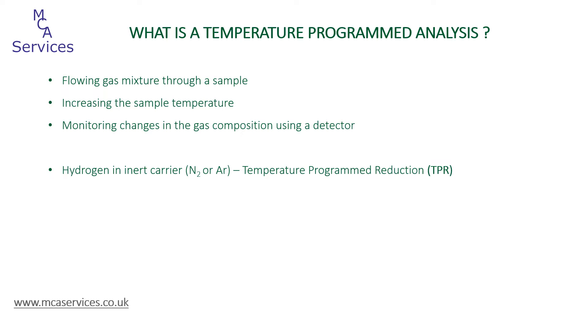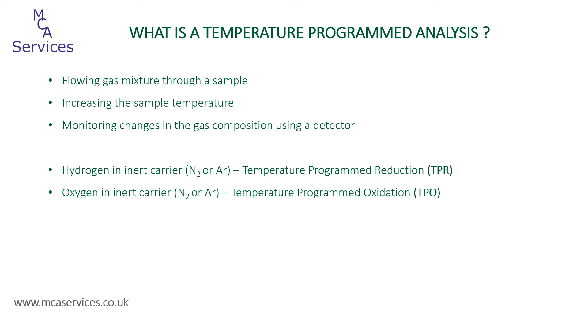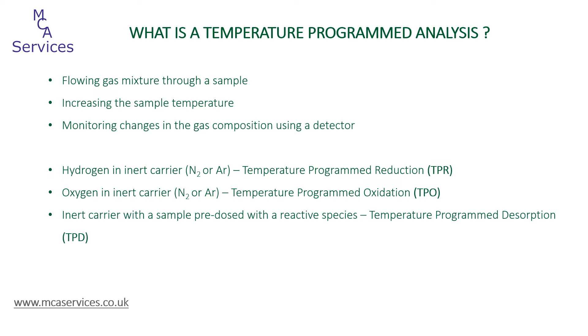Depending on our sample material and the components of the gas mixture, we can perform different temperature programmed analyses. If our sample can be reduced and we have a reducing agent in our gas mixture, for example hydrogen, we can undertake temperature programmed reduction. The opposite — we can oxidise a sample if we have oxygen in the carrier gas. A slightly more complicated analysis is temperature programmed desorption. For this, we pre-adsorb a species of our choosing onto a sample, and then we measure the rate at which it comes off — desorbs from the sample — as temperature is increased.